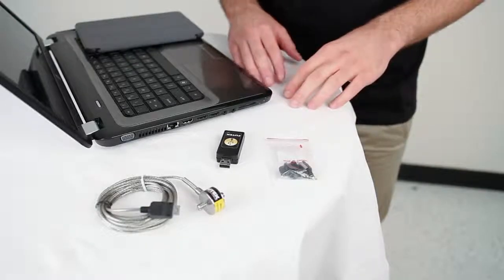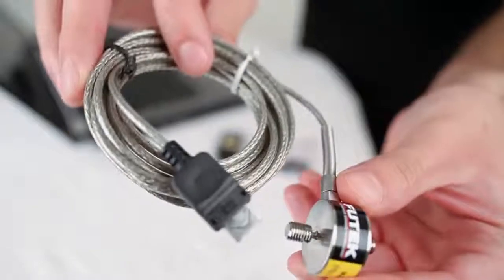In order to perform the USB calibration, you'll be needing a FUTEK USB device, the USB connector kit, or a pre-assembled connection to your sensor. Keep in mind that if you have a pre-assembled connection, please skip the wiring part of this video.